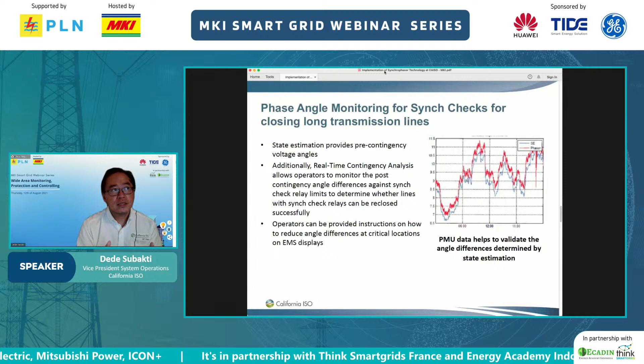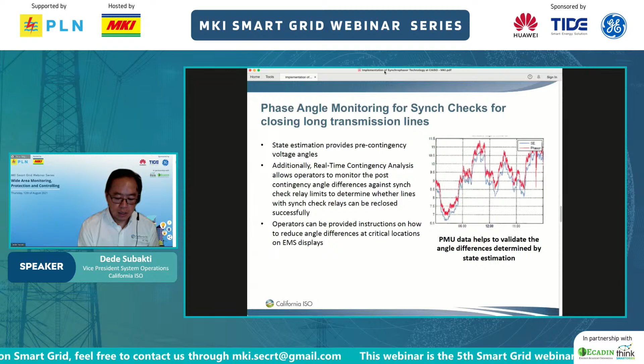They just know that when the line is open, they have to close it, and they have to have a sync check. They have to make sure that the delta angle, which is the voltage angle, is close enough. So for us it's very simple: you can calculate an angle using a PMU, so you know whether or not this transmission line can be closed in. If the angle is too wide, you move the generation. Once the angle is close enough, then you can close it. It's a very simple application of PMU that integrates it into the normal manual control of a human being, and that gets the operator to feel comfortable and used to this.